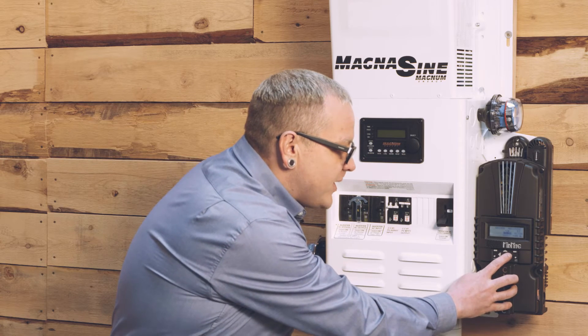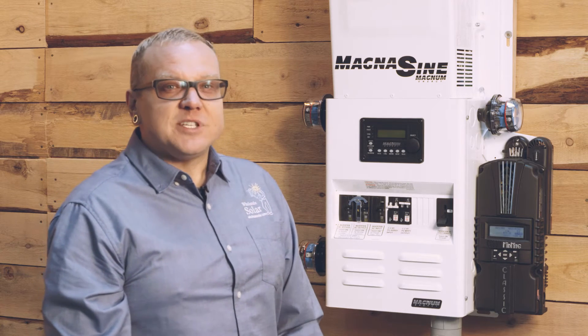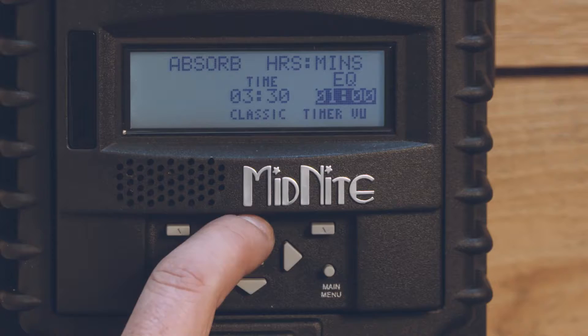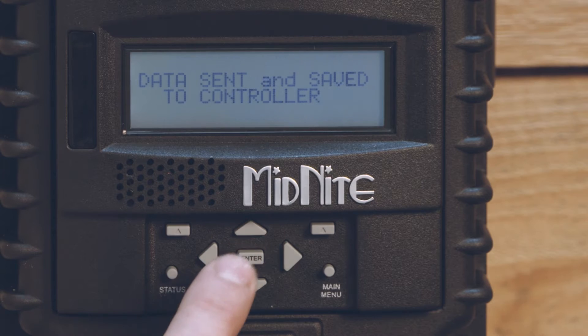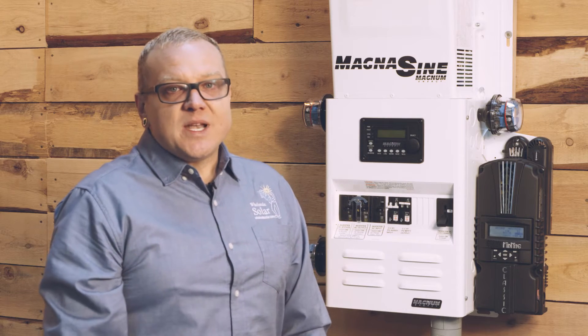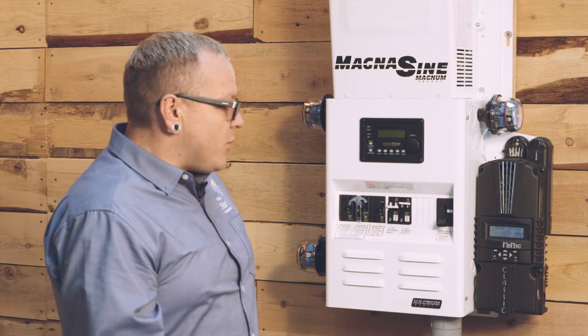I've got three hours and 30 minutes. Here's a pro tip: you've got to make sure that your equalization time is about one half to two thirds of what your absorb time is. If we're going to absorb for three hours and 30 minutes, we're going to start with an equalization time of two hours. So we'll get two hours programmed in here, hit enter, it'll flash 'data sent and save to controller.' That's all we need to do for the MidNite Classic 150 charge controller. The main thing we need to focus on is charging your batteries at the right voltage for the right amount of time, and that's what we're accomplishing here.